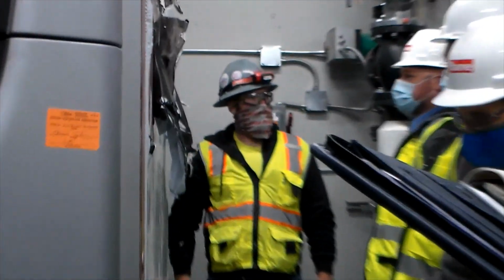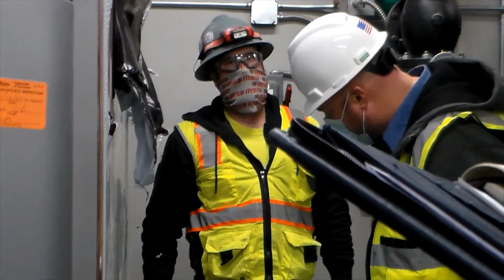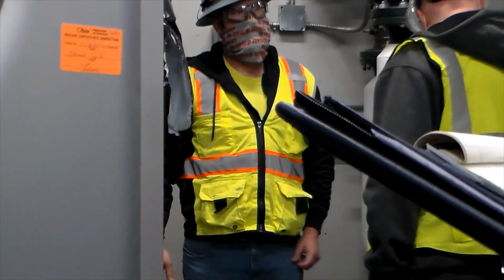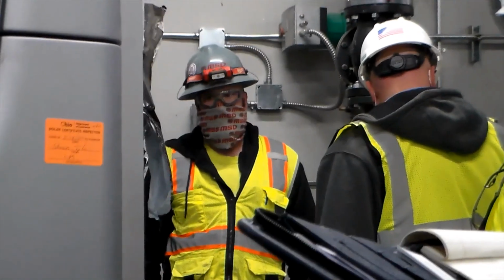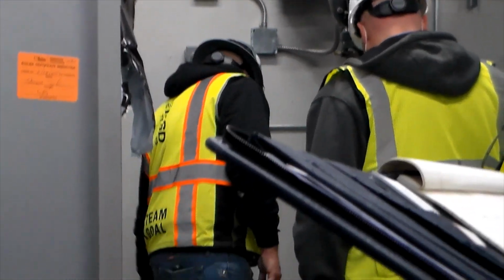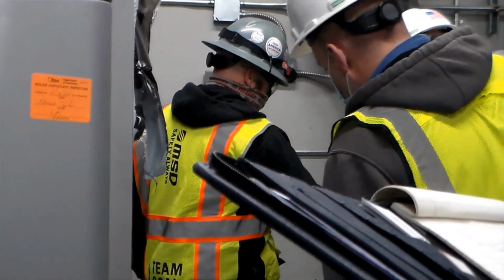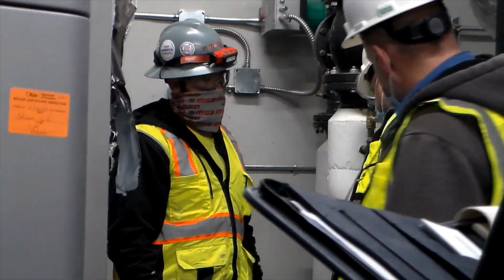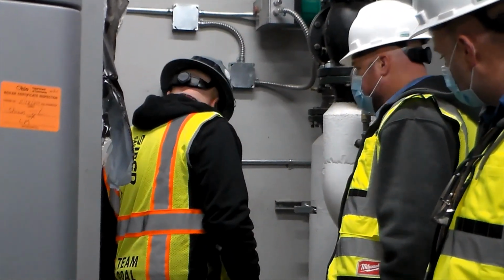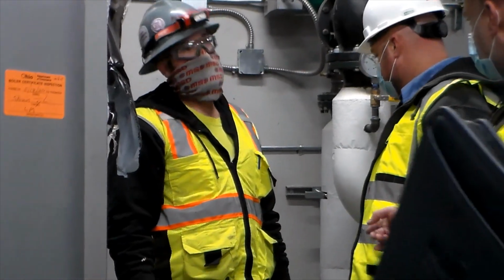You say do that yearly? The filter I do two times a year. Yep. And have a combustion test done one to two times a year. Your typical maintenance on a condensing boiler. Once a year. Yep.